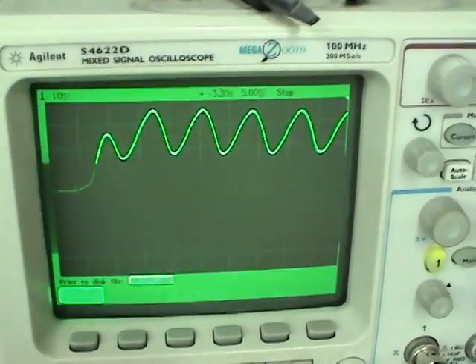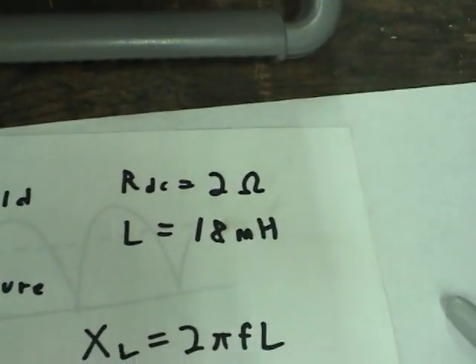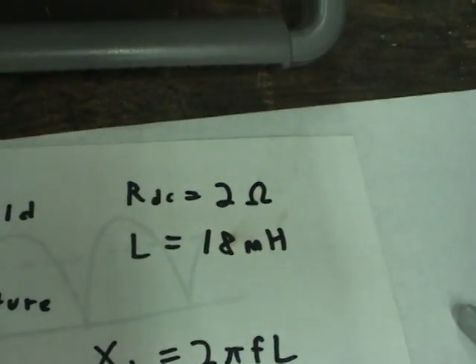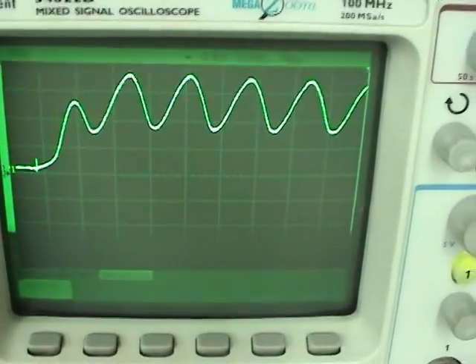And the DC current level we measure here is pretty close to what we predict based on 2 ohms. 120 volts over 2 ohms equals about 60 amps. We're getting about 50 here, probably due to the voltage drop due to all the wiring.